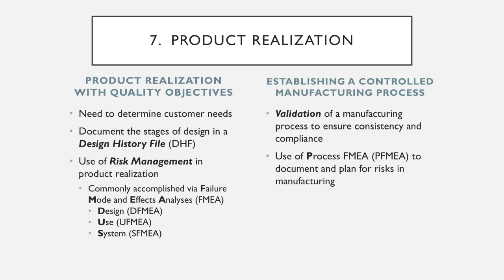And that's where, as an engineer, we need to actually look at what customer needs are and design devices that revolve around those particular needs. Now, a core part of documenting that is what's called a design history file. A design history file, or a DHF, is the documented record of how a medical device was designed. It shows how the device was developed in accordance with approved design controls. And it's a fundamental requirement under Title 21, Part 820 for devices subject to design controls.